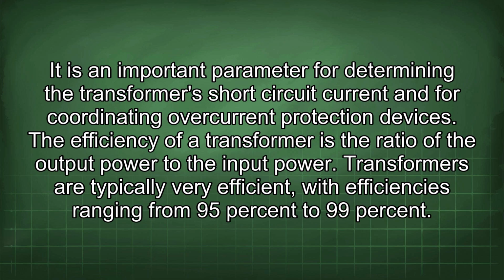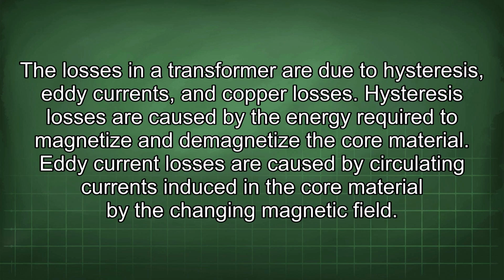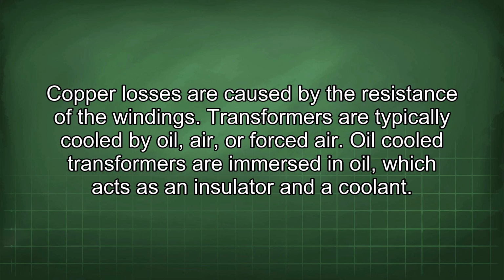The efficiency of a transformer is the ratio of the output power to the input power. Transformers are typically very efficient, with efficiencies ranging from 95% to 99%. The losses in a transformer are due to hysteresis, eddy currents, and copper losses. Hysteresis losses are caused by the energy required to magnetize and demagnetize the core material. Eddy current losses are caused by circulating currents induced in the core material by the changing magnetic field. Copper losses are caused by the resistance of the windings.